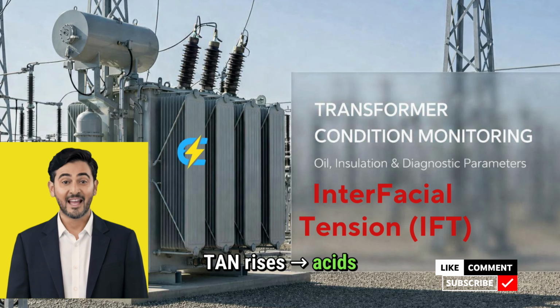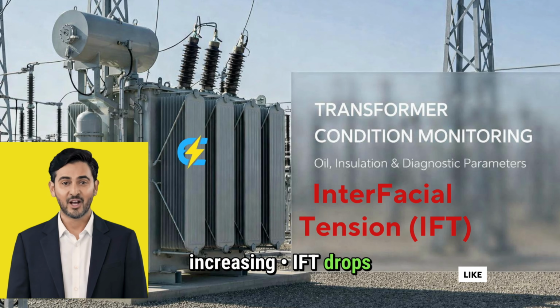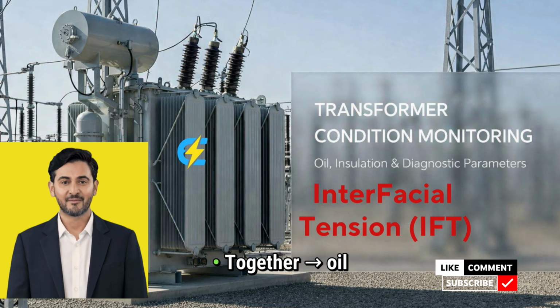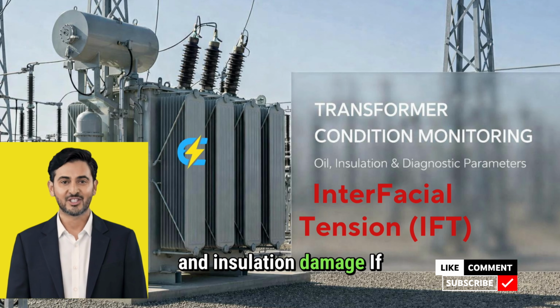TAN rises, acids increasing. IFT drops, polar contaminants increasing. Together, oil is moving toward sludge and insulation damage.